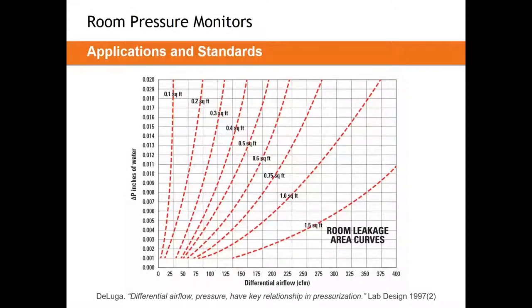Before we get into how to use monitors in these applications, it's important to understand what our role as design engineers actually is. To create room pressure we need to use a differential airflow between supply and exhaust. For example, if you understand the leakage rate of a space at one square foot, you could recreate room pressure of 0.01 inches with about 250 CFM of offset airflow. Our job is not to ensure we maintain a certain pressure differential — that will be the balancing contractor's responsibility.